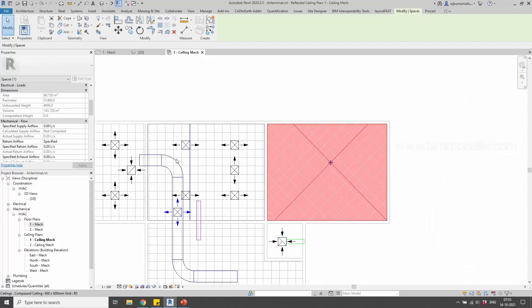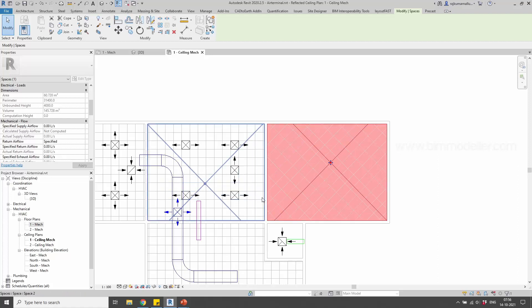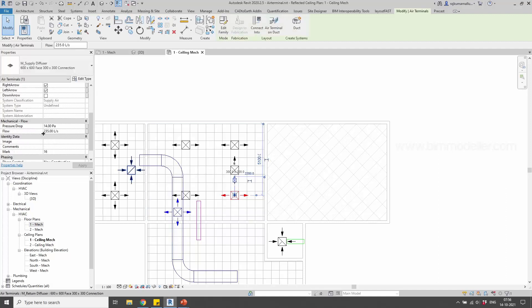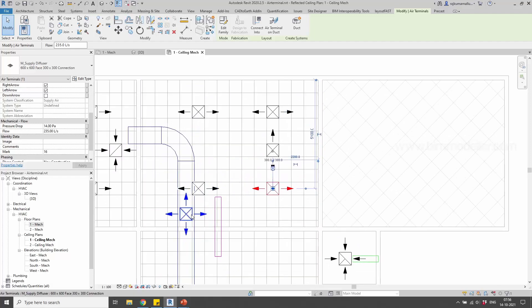On the bottom side you'll see some values. If you check your rooms, by default the space element has a property called 'Actual Supply Airflow,' which is zero by default. But after placing air terminals, your space will have a property value of 1175 — because we placed five air terminals with a supply value of 235 liters per second each. The pressure drop is 14 PA, and based on that it will be calculated.